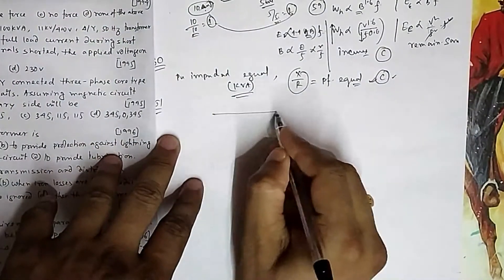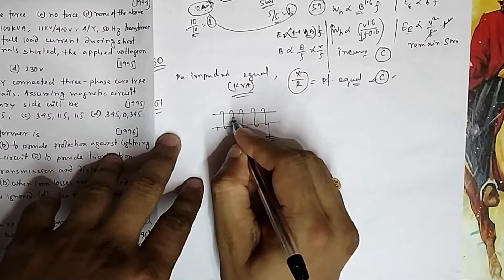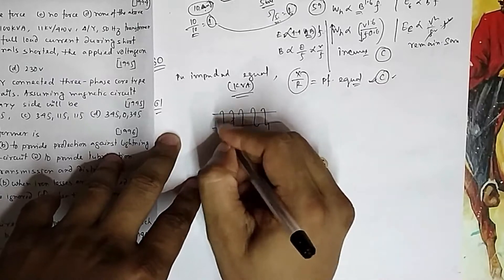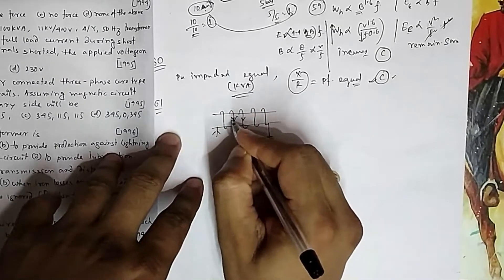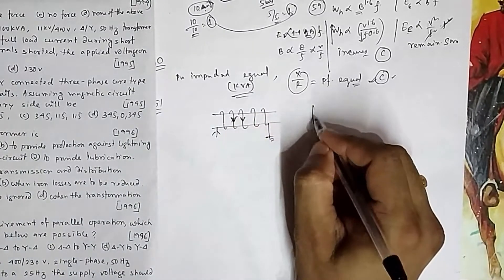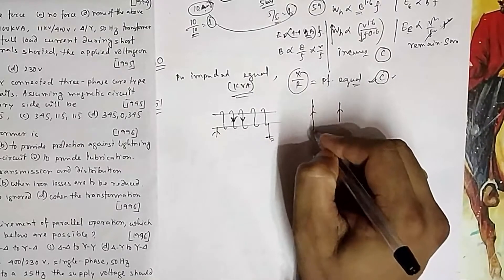Question 61: When a transformer winding suffers a short circuit, the adjoining turns of the same winding experience heavy current flow. Suppose this is my winding and it gets short circuited — the current flows in the same direction in these two adjacent windings. So these are like two parallel conductors with current in the same direction, meaning they will attract each other.